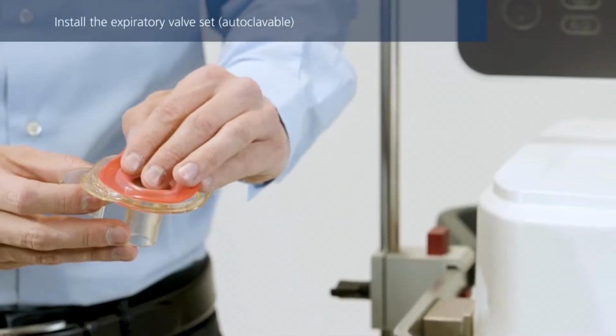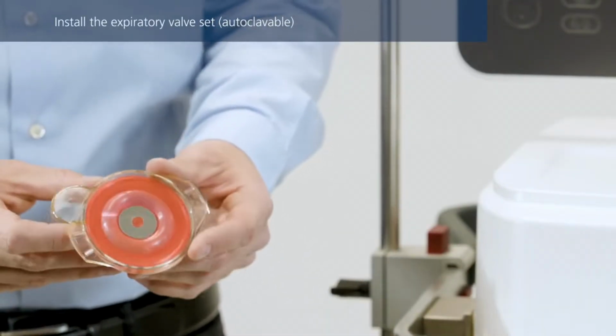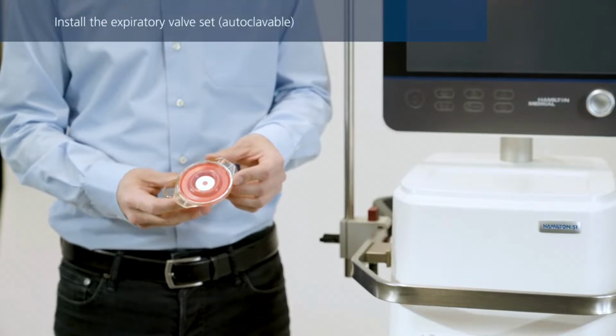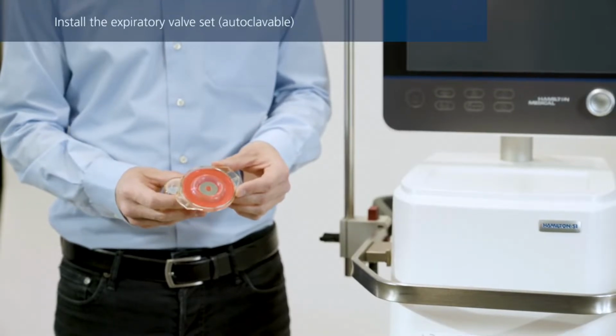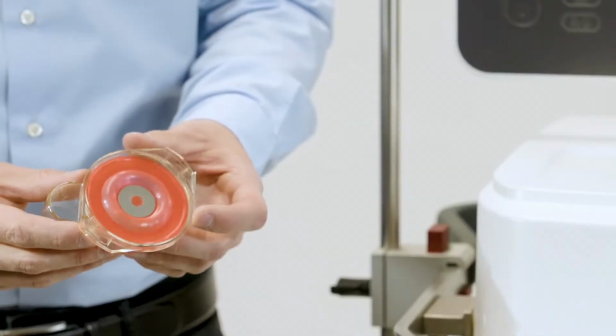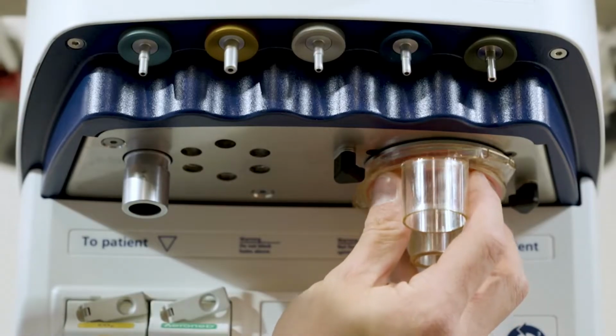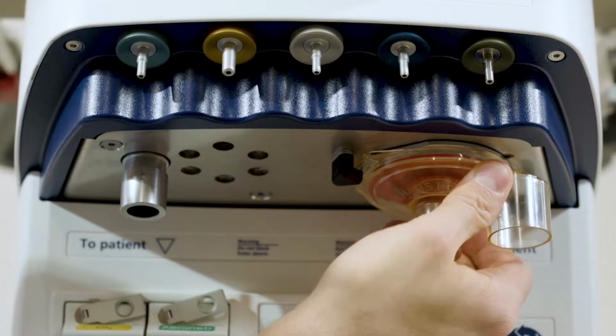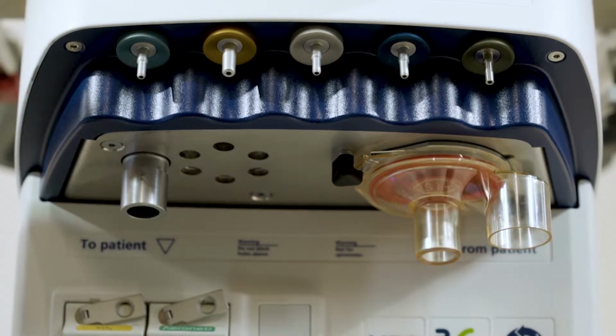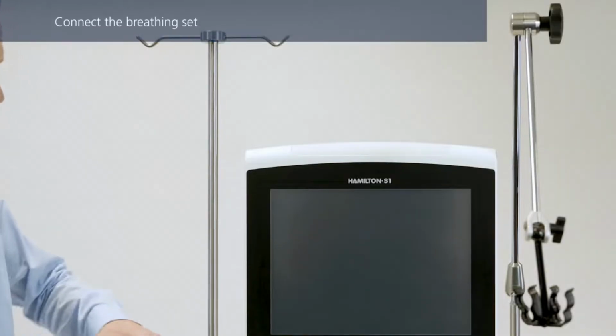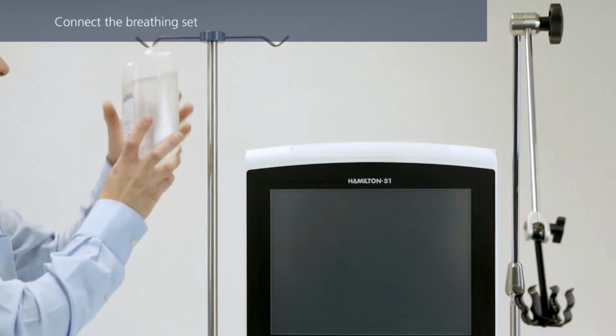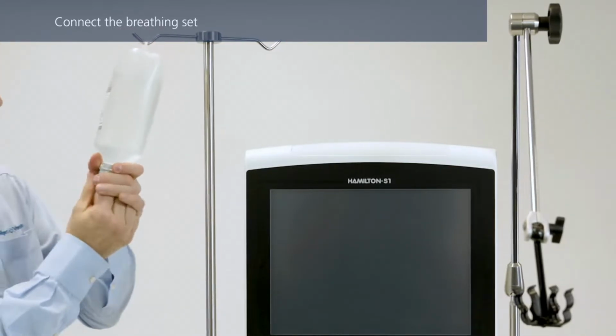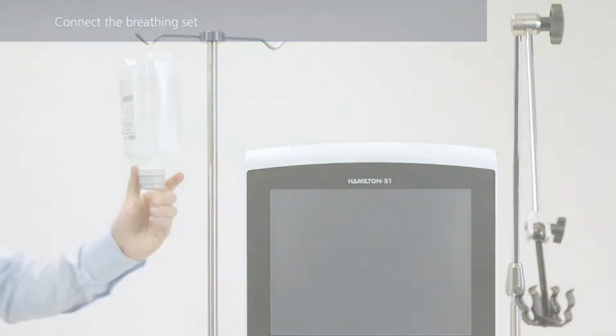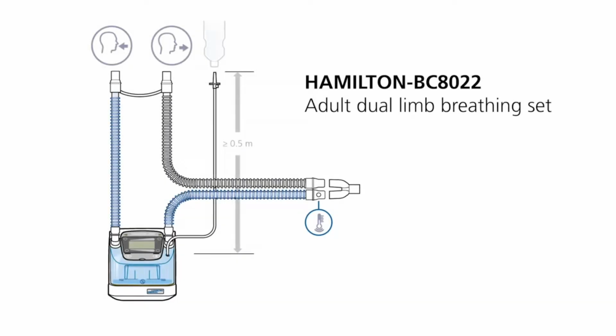If you are using an autoclavable expiratory valve set, first assemble it by placing the silicone membrane onto the expiratory valve housing. Ensure that the metal plate is facing upwards, and then proceed with the installation. The procedure is the same as for a single-use component. Install a water bag or bottle above the humidifier. Choose the correct breathing circuit according to the patient group or selected treatment.